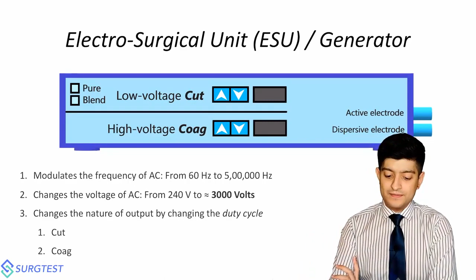The cut setting has the usual color coding of yellow, and there's coag color coded as blue. Within cut, you have a choice of several different settings, most commonly a choice between pure cut and blend mode. Beyond that, you have numbers which are put up.